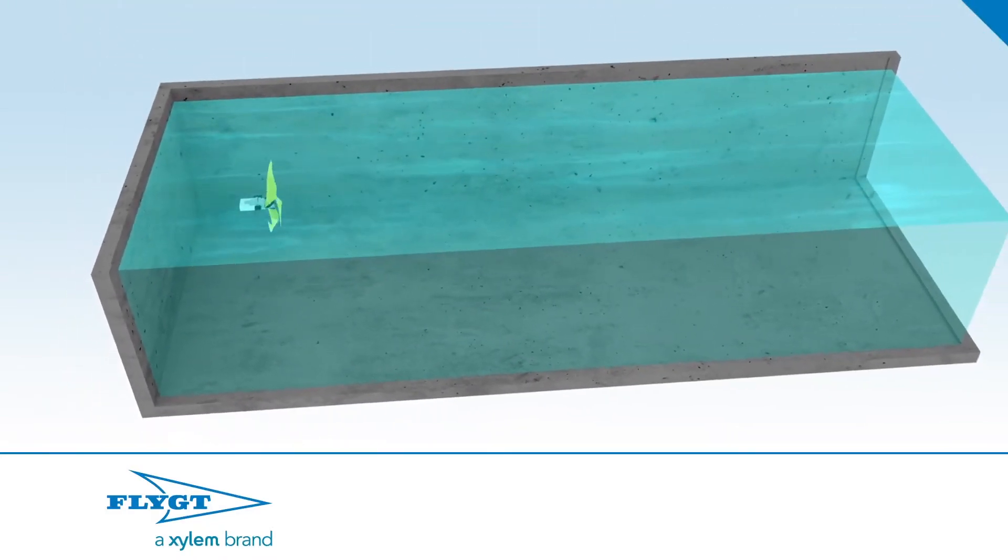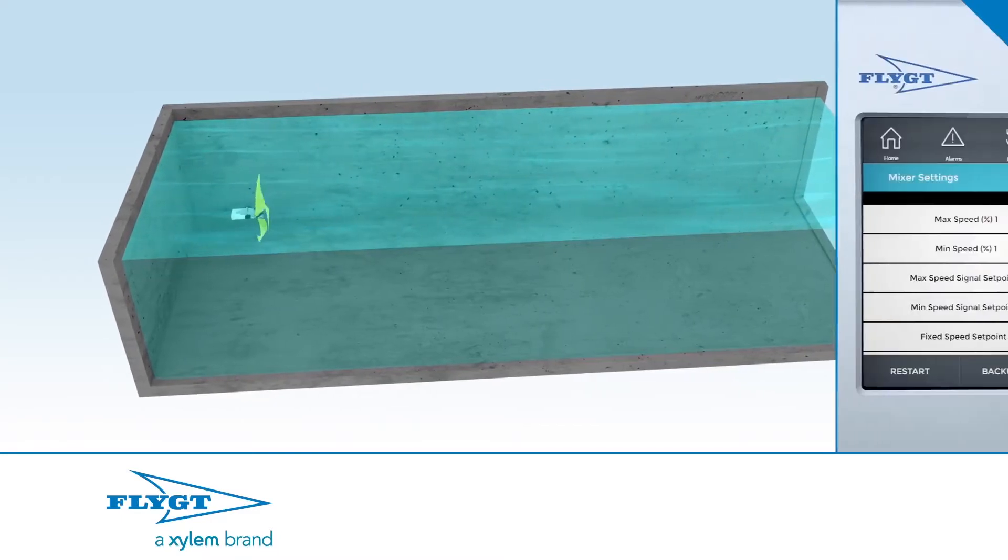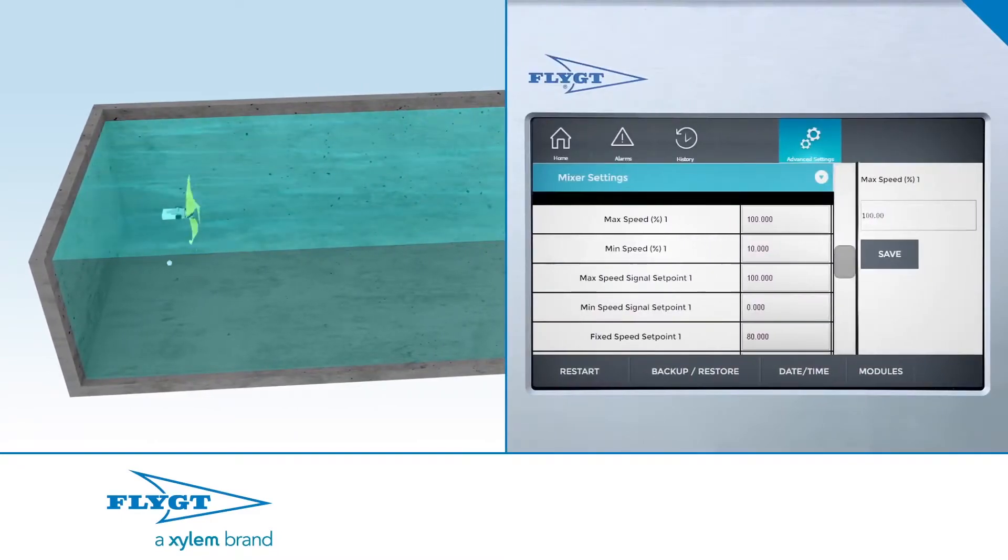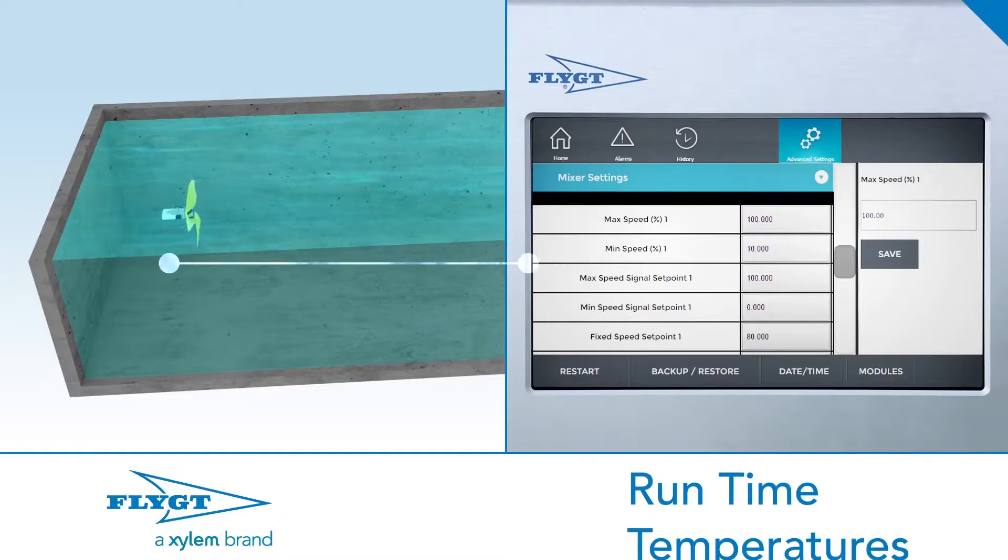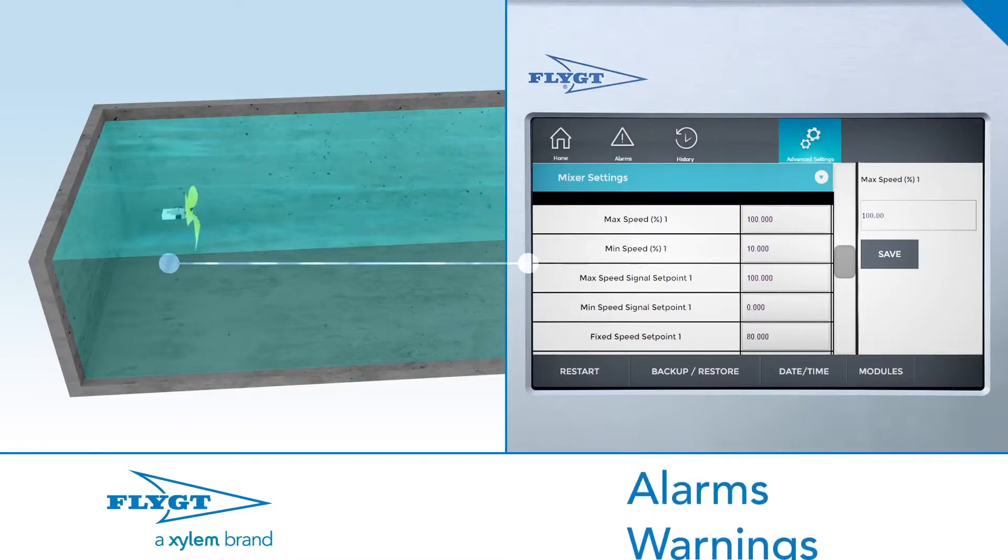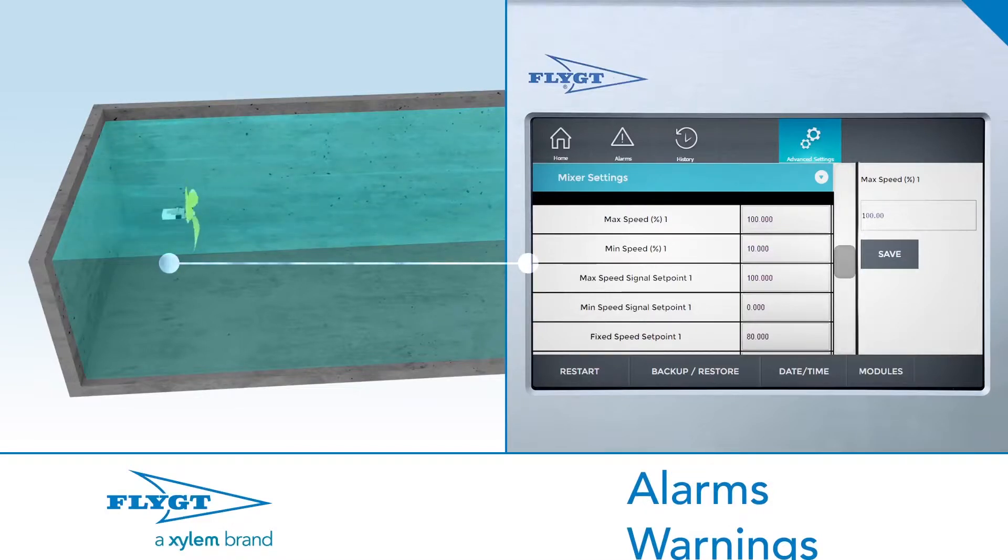Variable speed mixers have other advantages as well. For example, the Flygt 4320 is equipped with advanced communications, so you know what is happening below the surface. The 4320 knows its speed, power consumption, temperatures, run time, and more. And it communicates this information, along with any warnings or alarms, continuously via a variety of connected devices utilizing Modbus and other protocols.